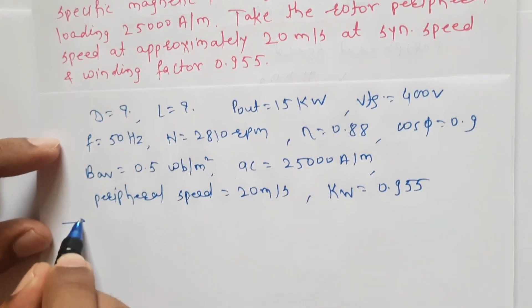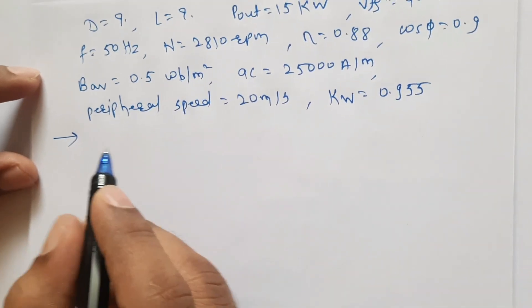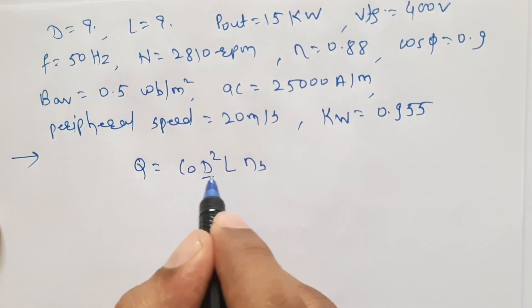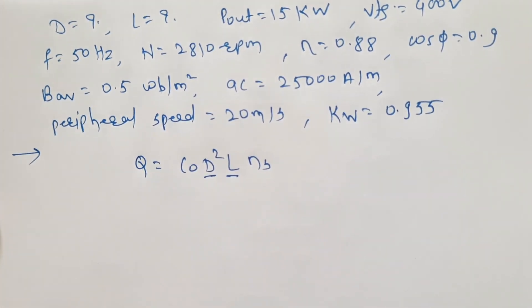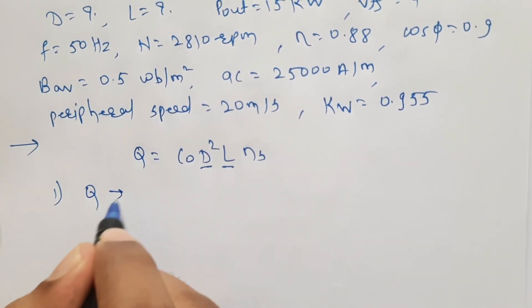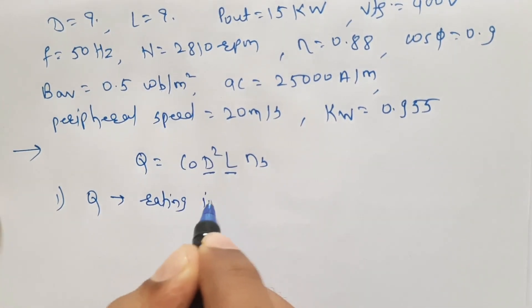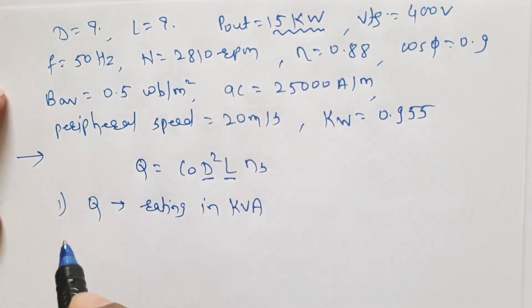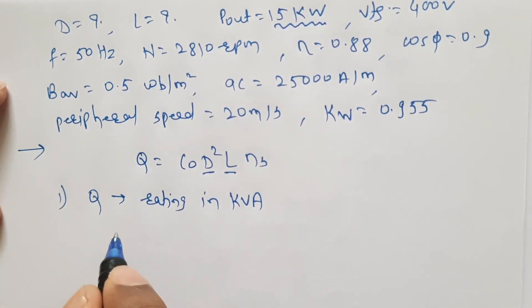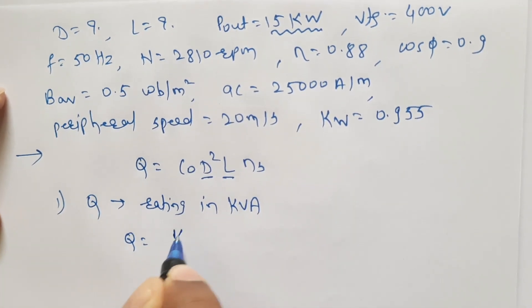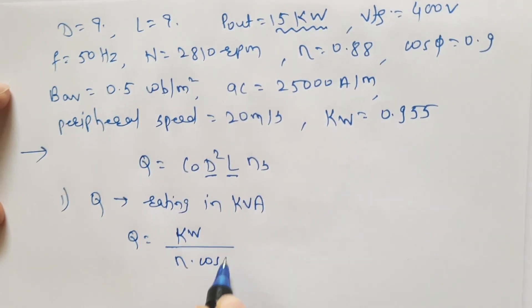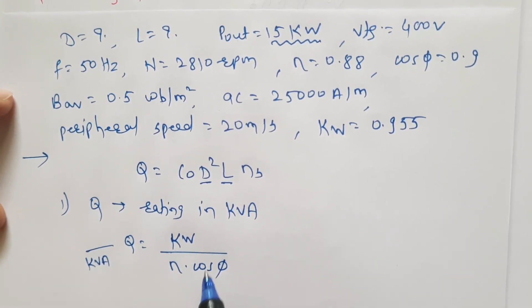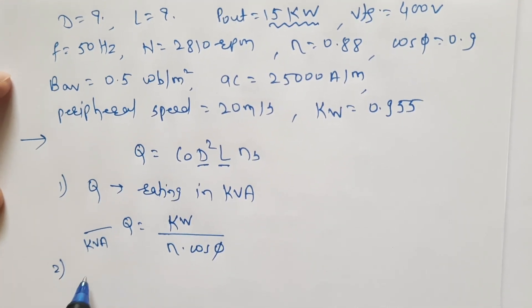Now we will understand how to solve the problem. We know the output equation of induction motor: Q equals C0 into D-squared L into Ns. Since we have to find D and L, the main dimensions of the motor, the first step is to find Q. Q is the rating of the motor in KVA, but in the given data the motor output is given in 15 kilowatt.